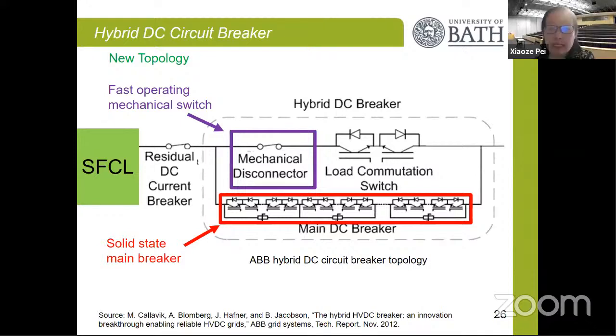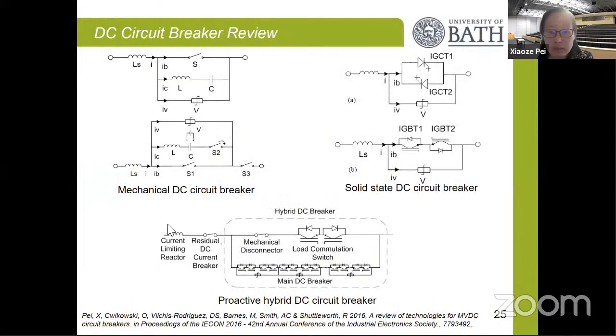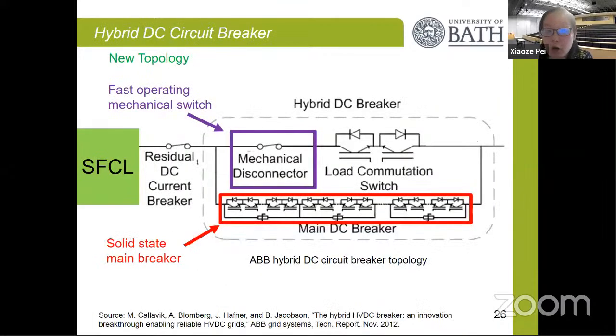Okay, so to improve the efficiency means the reduction of the losses. Originally you can say it is using the current limiting reactor, and this current limiting reactor would have losses during the normal operation as well. That is why we propose to use a superconducting fault current limiter. In this case, it almost has no losses during the normal operation. And then the second component is looking into the losses for the primary path that current normally goes through.